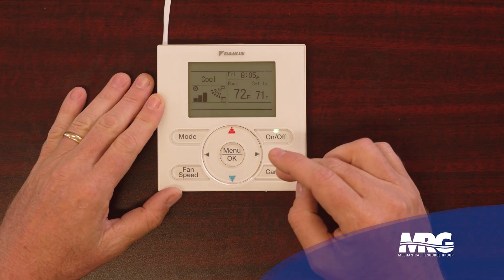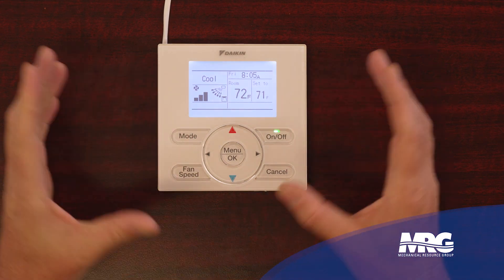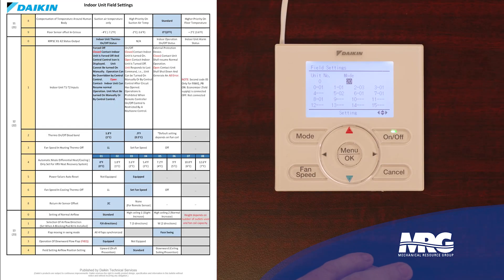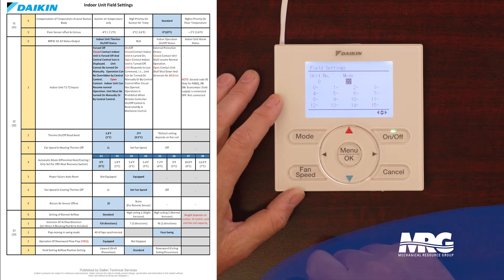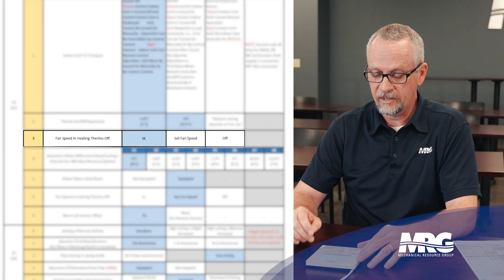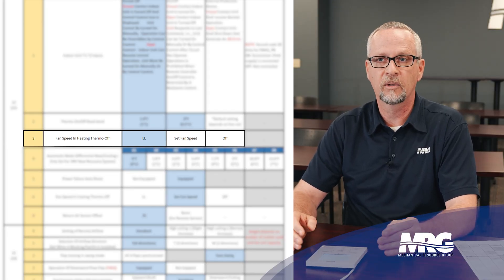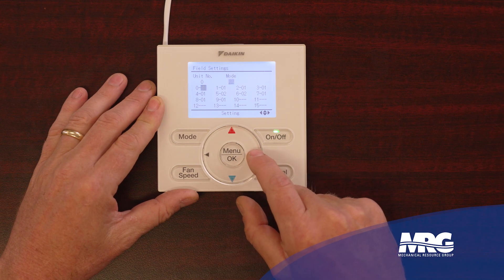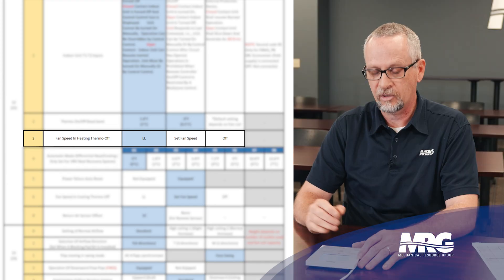To do that, we're going to enter setting mode 22. Again, we're making an individual change — if we were going to do a group change it would be setting mode 12. We're going to enter our service settings mode and scroll down to field settings again. Now we're going to go to setting mode 22 and let it populate. The changes I need to make are to number 3-01 and number 6-02. We're at the default for 3-01 — that's telling me the fan speed runs at low-low. We need to change that so when the heating satisfies, the fan shuts off. This will create nuisance callbacks where the customer says my unit is satisfied but the fan never shuts off. So we're going to select setting mode 3-01 and change it to setting mode 3-03. That takes care of our heating — now the fan will completely shut off when we satisfy our heating set point.